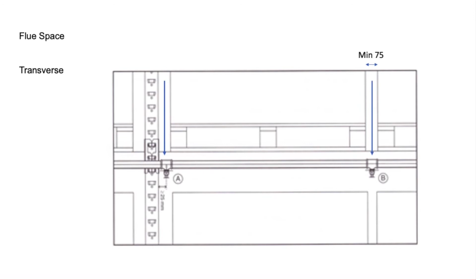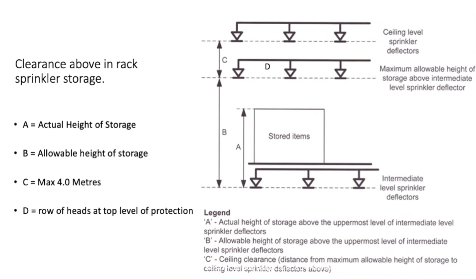Okay. When you get to the top of the racks, again, we protect the top level of the rack. So the A dimension is the actual stored height of the goods. The B dimension is the allowable storage height, depending on the density of the roof. And the C dimension is 4 metres maximum. Now, in this instance, you shouldn't be adding more density at the roof. What you should be doing, you should put another row of heads at the top level of the racks, above the top level of the storage. And that's only if your C dimension is more than 4 metres. Okay.